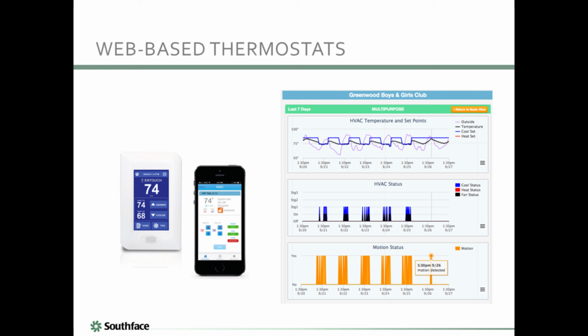It's recommended that you install internet accessible thermostats, or web-based thermostats, for rec centers that have unitary equipment. Enable the smart recovery or optimal start feature such that the system start time is determined algorithmically so that the building reaches set point by the scheduled occupied time. Setting up schedules that match the operating schedule of the building, and setting temperature set points during unoccupied periods can produce big savings. Setting the thermostat back to 60 degrees during heating mode or 85 degrees during cooling mode is recommended.